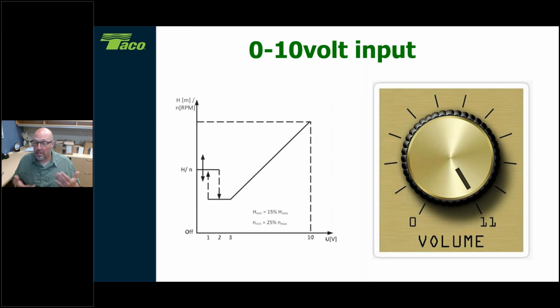There are some boiler manufacturers that have a 0 to 10 volt output to tell the circulator what speed to run at, so the boiler is as efficient as it can be at the time. It might be looking at a delta T across the heat exchanger to add efficiency to the system, because it doesn't want to run full speed all the time, since you're not taking everything out of the boiler all the time. So let's slow the circulator down, gain the most efficiency, condense when it's supposed to, and maintain that condensing.